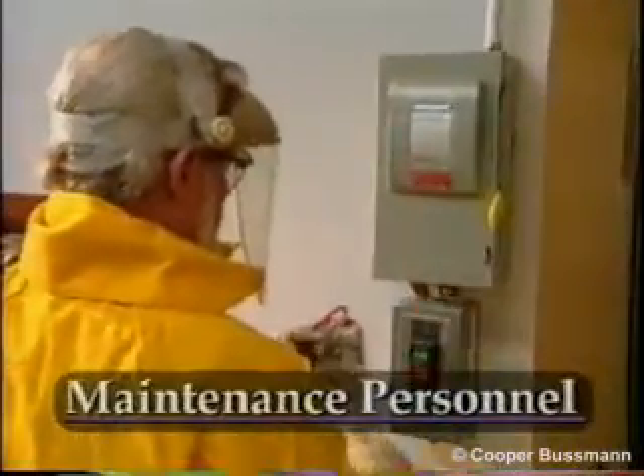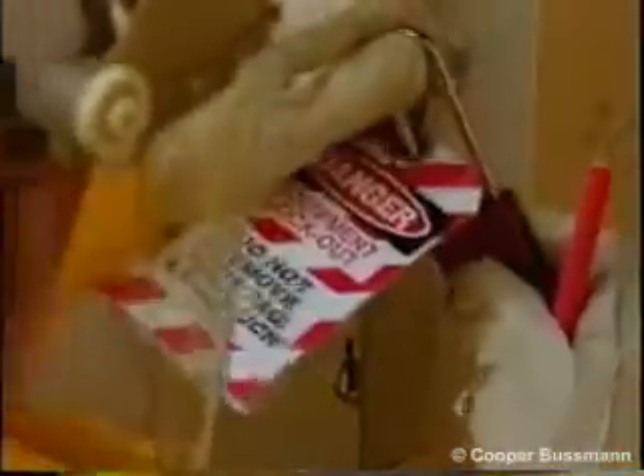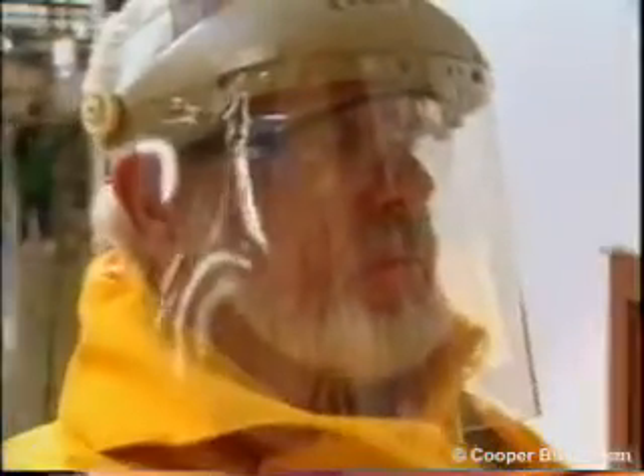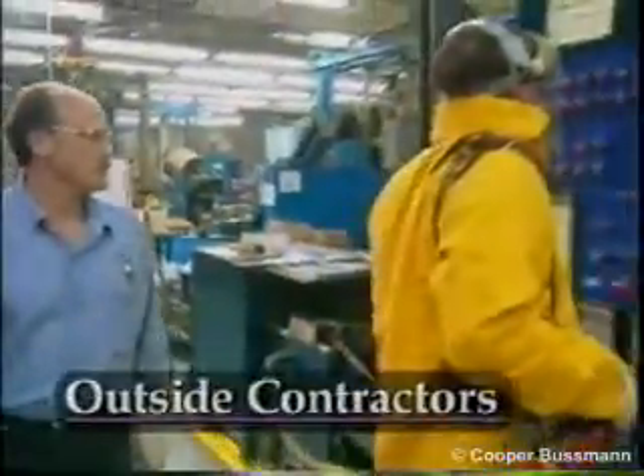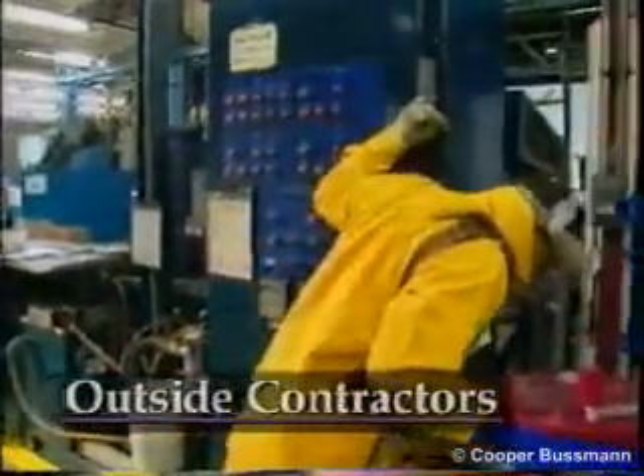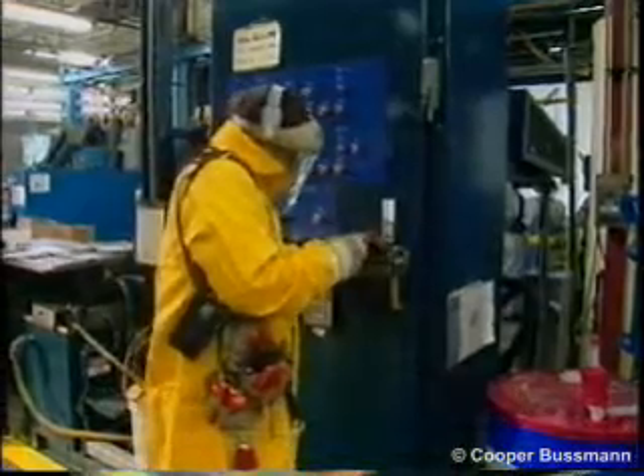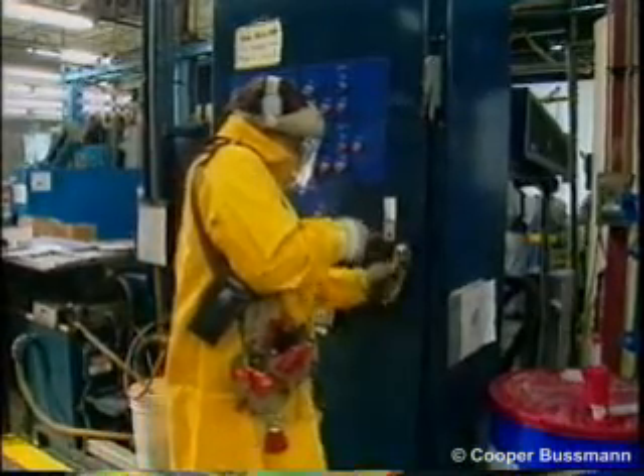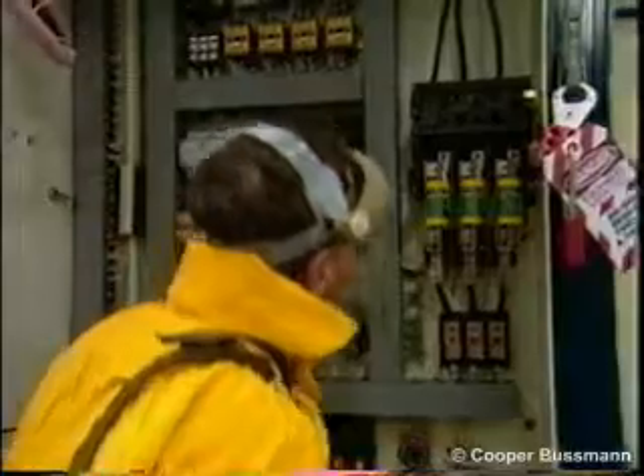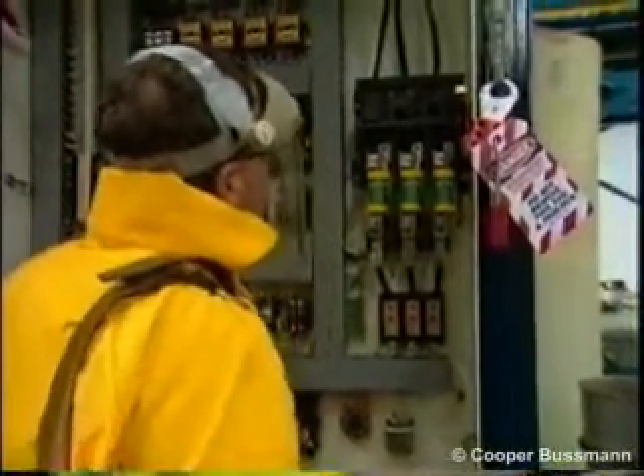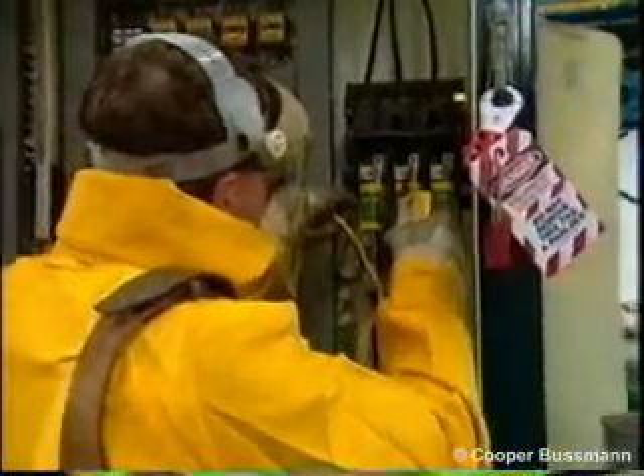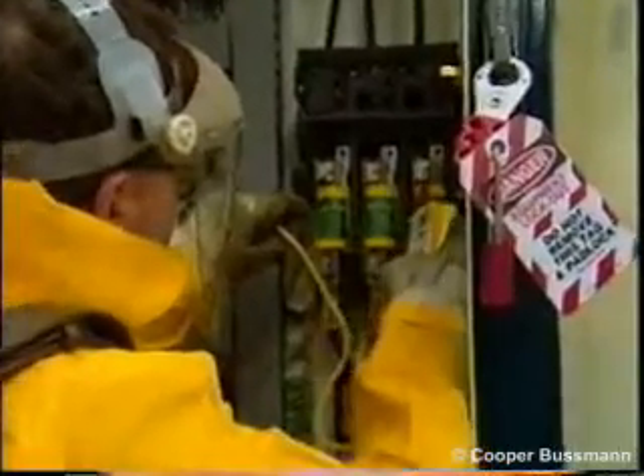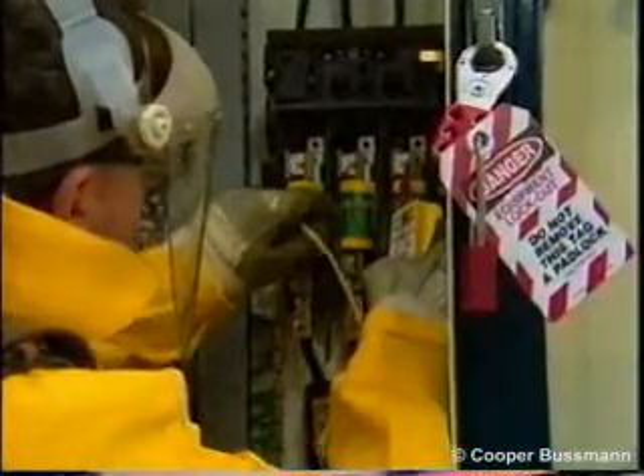Maintenance personnel must take all necessary steps to assure that the system on which they plan to work is de-energized and properly isolated. They are also responsible for individual personal protective devices, such as locks and tags. Outside contractors must also possess a thorough understanding of the system, including how it can be isolated from energy sources. They must be aware of and able to comply with the company's safety procedures. And whenever possible, contractors should add their own lockout-tagout devices to appropriate isolation points.